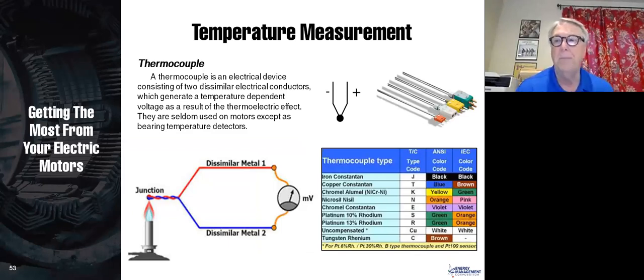This is a thermocouple. Now this is more what you see in your heavy-duty industrial motors. You can see there's lots of types of thermocouples, and they're based on the fact that when you take two pieces of metal and you connect them together here, they are going to create a voltage, and that voltage depends on what the two metals are, and it depends on the temperature of that junction. So there's a lot of them. There's iron constantan, those are the two metals, copper constantan, so on and so forth.